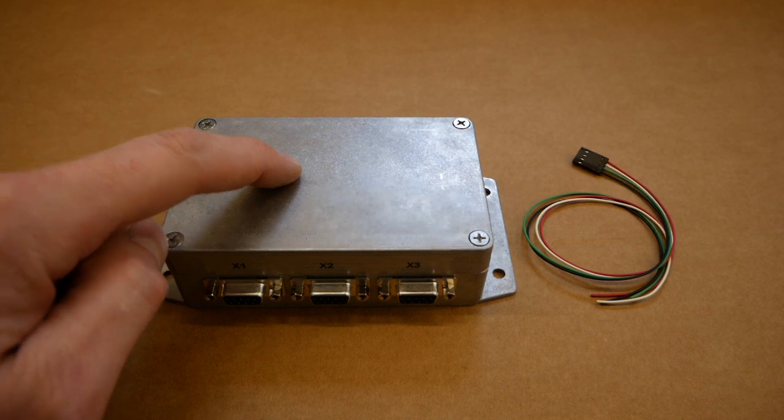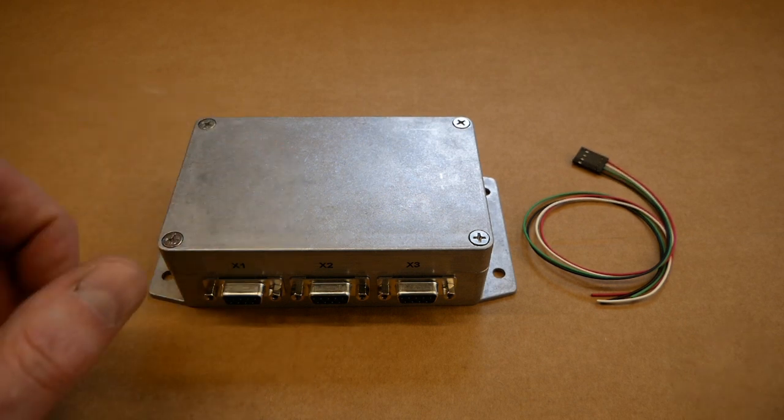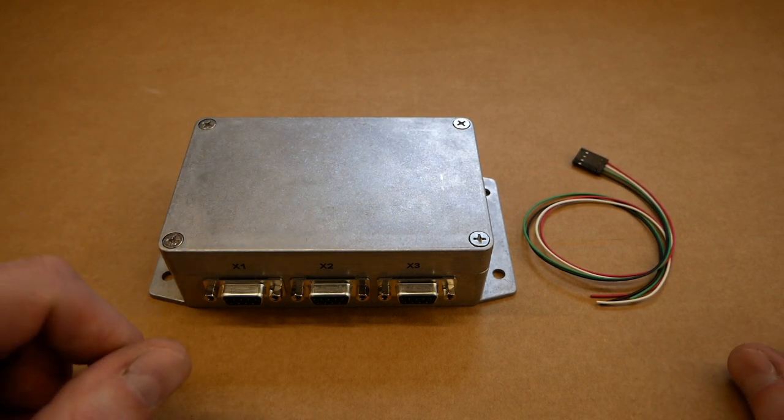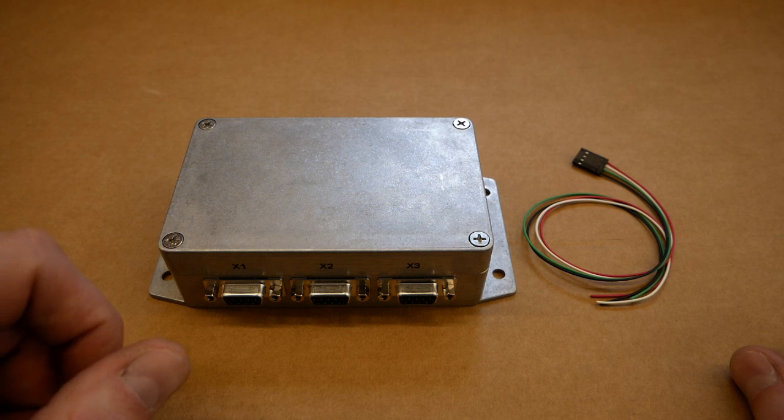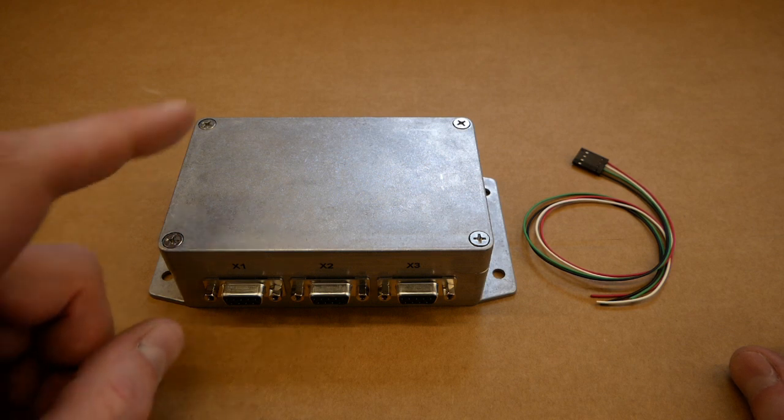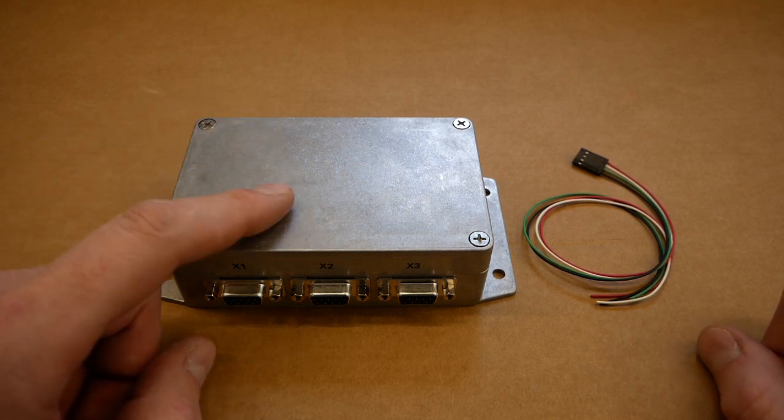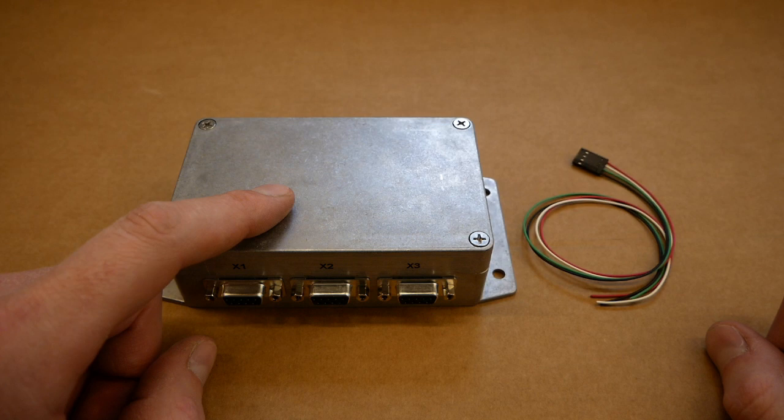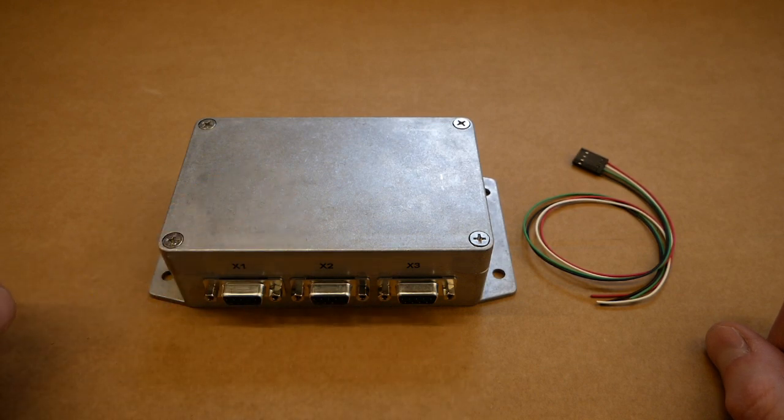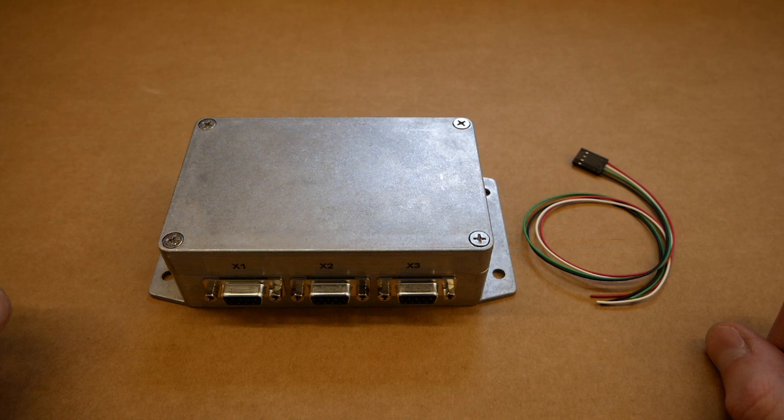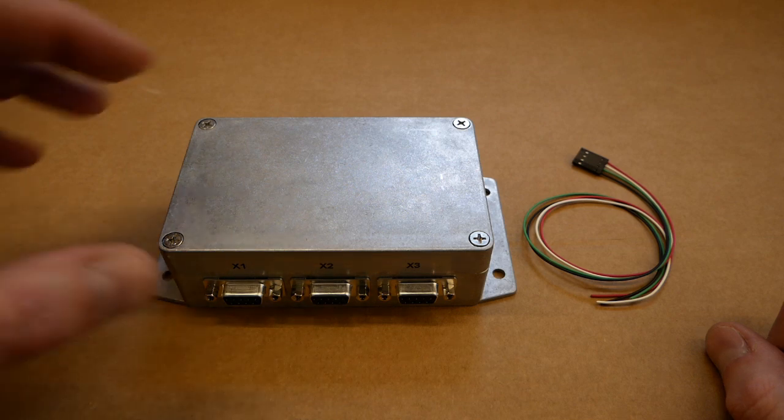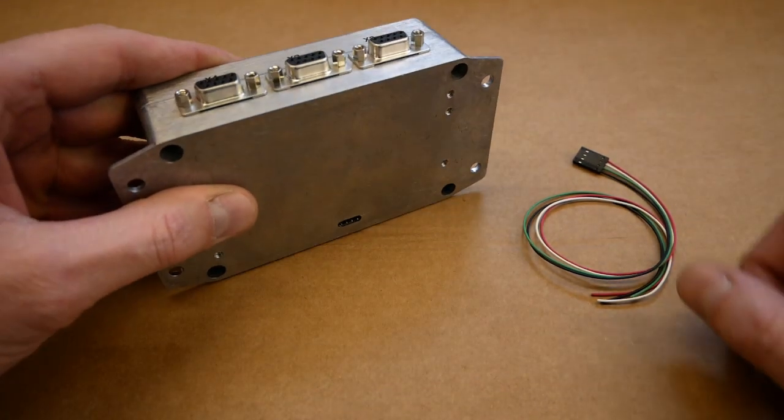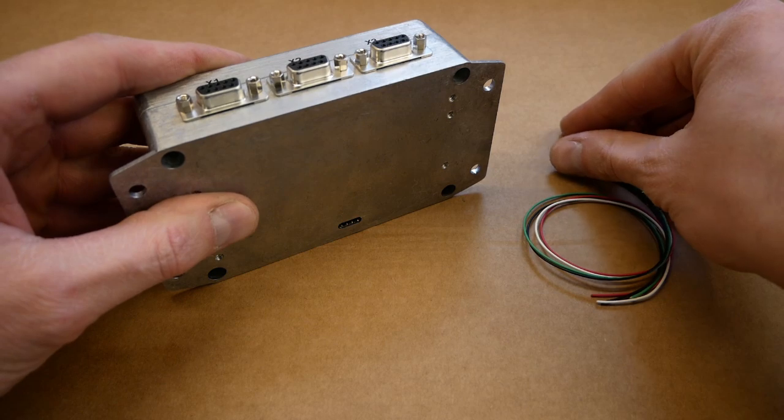The enclosure is full metal. This is important as it effectively shields the controller from EMI/EMC noise. The enclosure must be properly grounded for correct operation. It has three connectors on the front and one connector on the bottom. The load cell connects to the bottom connector like so.